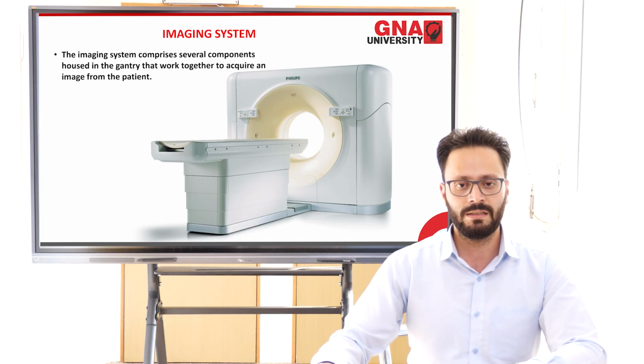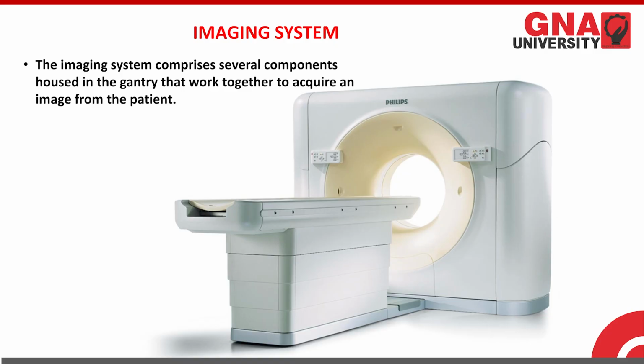Now about the imaging system. The imaging system comprises several components housed inside the gantry that work together to acquire the image from the patient. So we have multiple pieces of equipment placed inside this particular structure. This is known as the gantry, and its primary purpose is to produce X-rays that will go through the body of the patient, and on the other end, those X-rays will be taken up by the detectors. To support that function, there are multiple other electronic equipment present within this gantry.